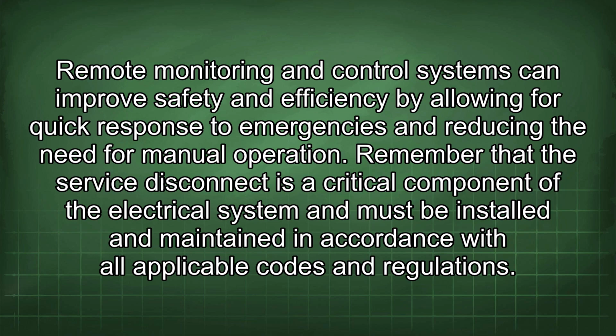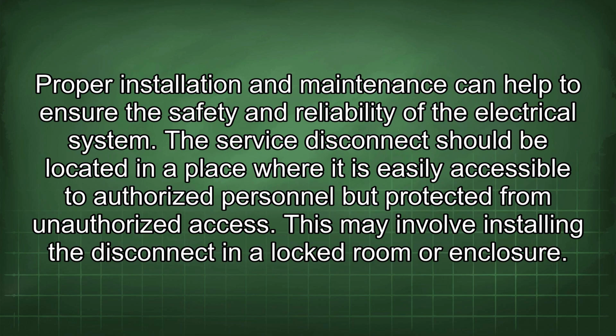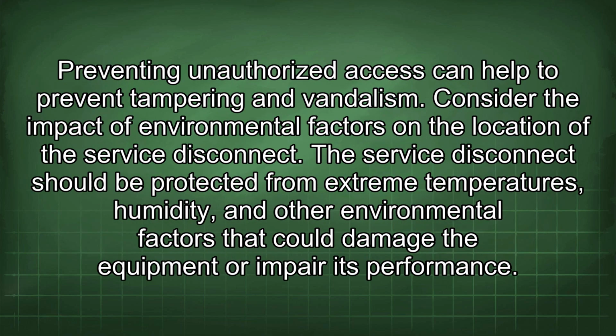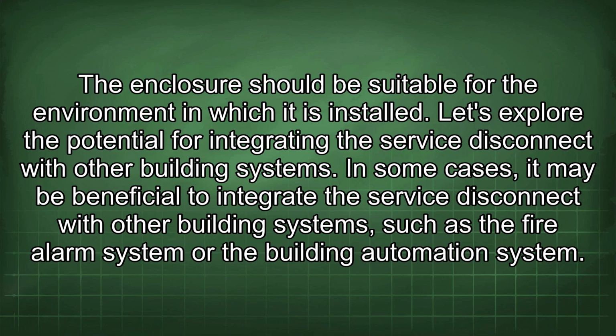Remember that the service disconnect is a critical component of the electrical system and must be installed and maintained in accordance with all applicable codes and regulations. Proper installation and maintenance can help to ensure the safety and reliability of the electrical system. The service disconnect should be located in a place where it is easily accessible to authorized personnel but protected from unauthorized access. This may involve installing the disconnect in a locked room or enclosure. Preventing unauthorized access can help to prevent tampering and vandalism. Consider the impact of environmental factors on the location of the service disconnect. The service disconnect should be protected from extreme temperatures, humidity, and other environmental factors that could damage the equipment or impair its performance. The enclosure should be suitable for the environment in which it is installed.